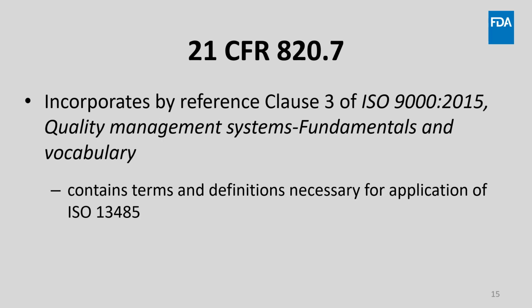Additionally, ISO 13485 has a normative reference, which we incorporated by reference into the regulation. This reference is ISO 9000-2015 Quality Management Systems Fundamentals and Vocabulary Clause 3, and it contains terms and definitions necessary for the application of ISO 13485.